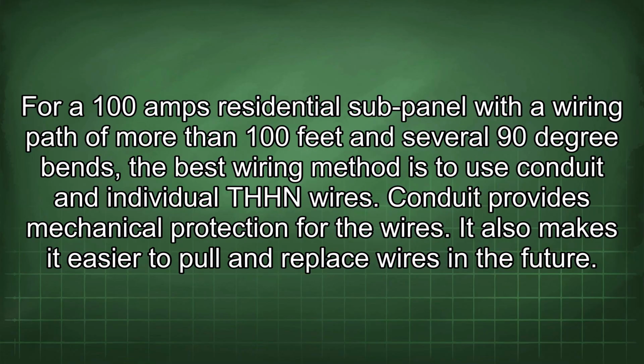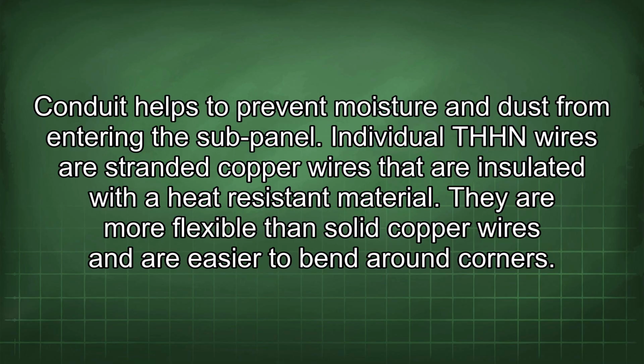For a 100 amp residential sub-panel with a wiring path of more than 100 feet and several 90-degree bends, the best wiring method is to use conduit and individual THHN wires. Conduit provides mechanical protection for the wires. It also makes it easier to pull and replace wires in the future. Conduit helps to prevent moisture and dust from entering the sub-panel.